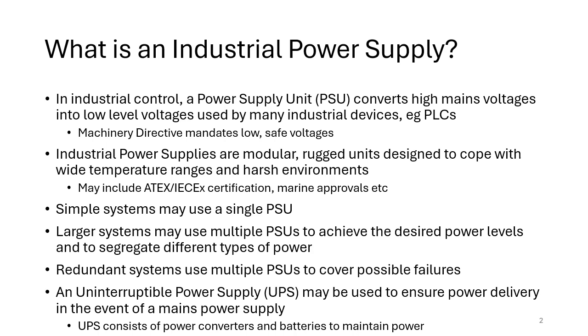Now, with a simple system, you may use a single power supply, but the downside is that a single power supply may not provide enough power, and you might also get noise coming between the different wiring systems. For example, outputs might interfere with inputs and might even interfere with the system because you can get noise transmitted on the power rails. So larger systems typically use multiple power supplies to achieve the desired power levels and also to segregate different types of power. In redundant systems, we also need to use multiple power supplies to cover possible failures.